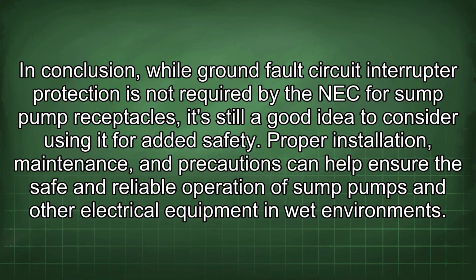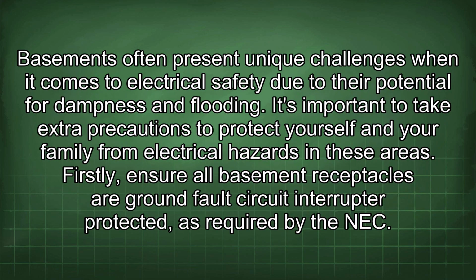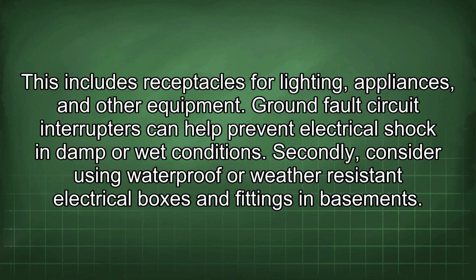Basements often present unique challenges when it comes to electrical safety due to their potential for dampness and flooding. It's important to take extra precautions to protect yourself and your family from electrical hazards in these areas. Firstly, ensure all basement receptacles are ground fault circuit interrupter protected as required by the NEC. This includes receptacles for lighting, appliances, and other equipment.